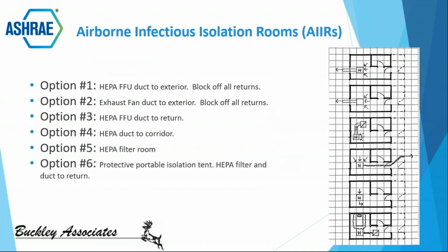So in this presentation, they laid out 6 different options for these temporary isolation rooms outside of their true design conditions, okay? These options are drawn out on the right side of this slide here, if you take a quick look. Option 1 on top shows a room with access to a nearby window. What they're recommending is a fan filter unit with HEPA filtration. So a HEPA filter thrown in this fan filter unit, and it's going to be used to exhaust air directly out of a sealed window.